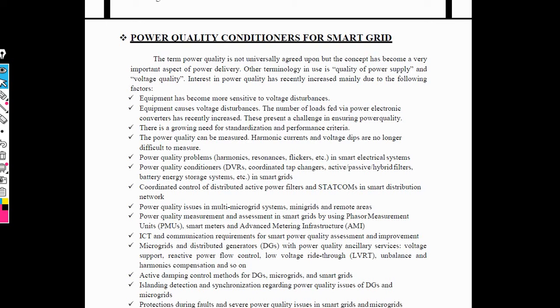Then the equipment required is more sensitive to voltage disturbance and current disturbance. But a large amount of equipment causes voltage disturbance due to the number of loads, and these loads will be connected to the power electronic converter. At that instant the voltage disturbance increases. Then we need the power quality conditioner. At that instant we need to study different parameters like harmonic voltage, harmonic current, voltage sag, and voltage swell. That means these are the parameters studied in power quality.